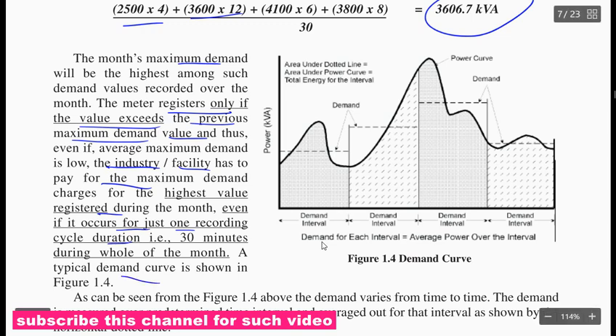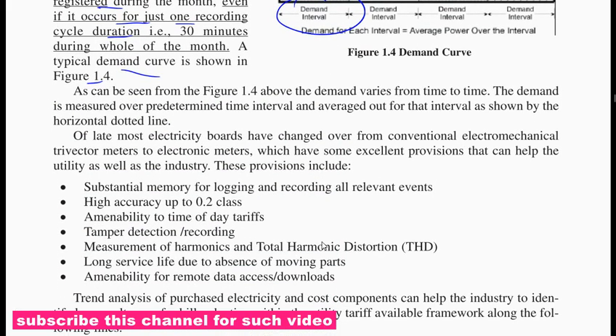A typical demand curve is shown in this figure. That is power drawn, that is demand. The interval is called the demand interval. It can be seen from the figure above that the demand varies from time to time. Demand is measured over a predetermined time interval, and the average over the time interval is shown by the horizontal dotted line.